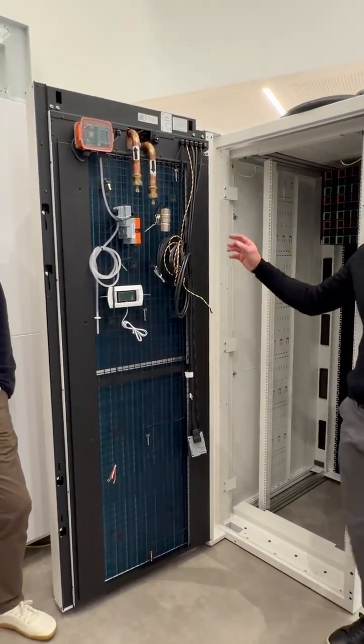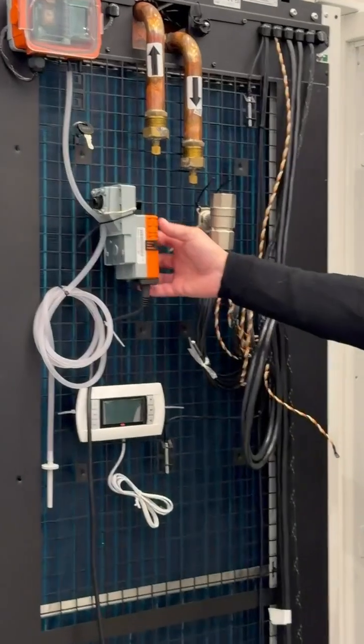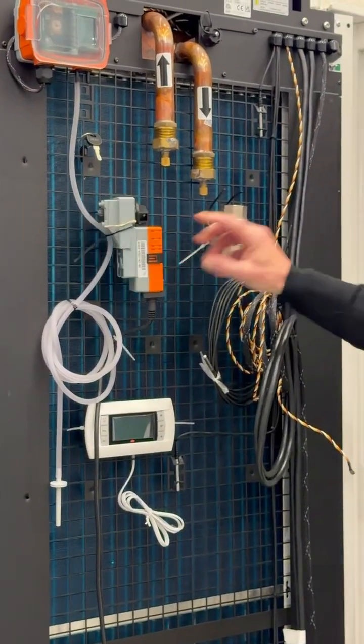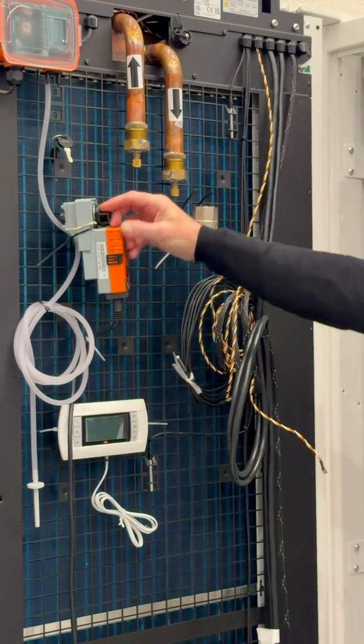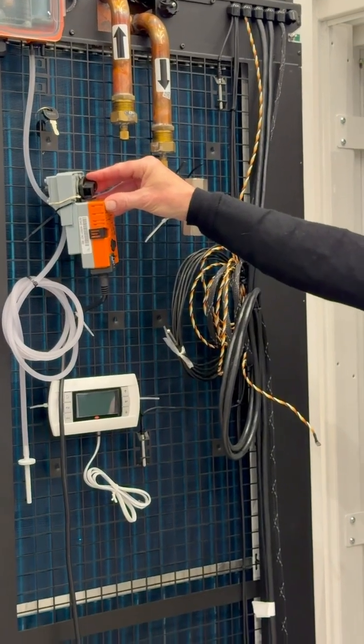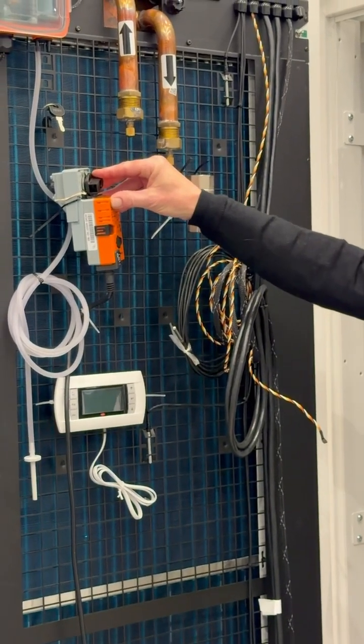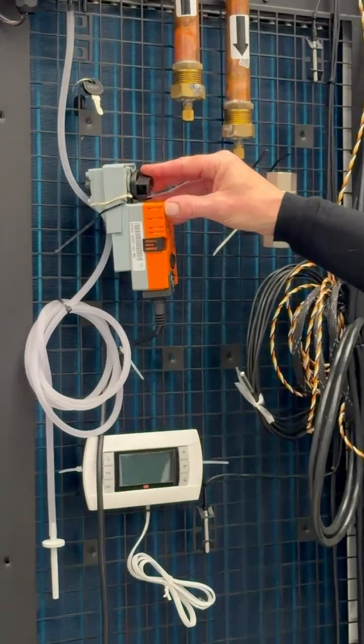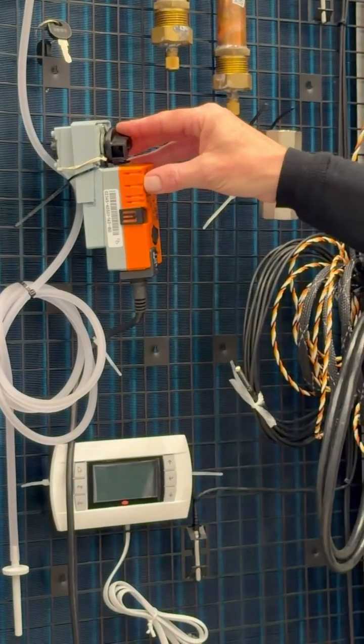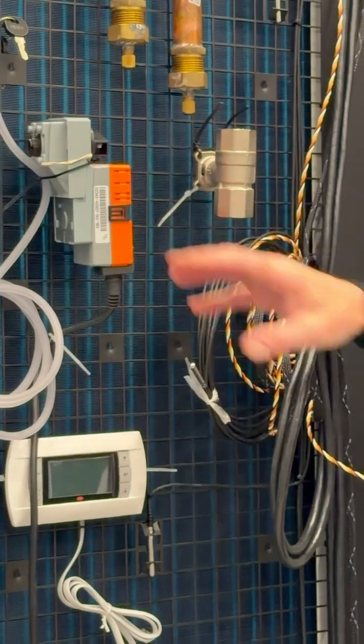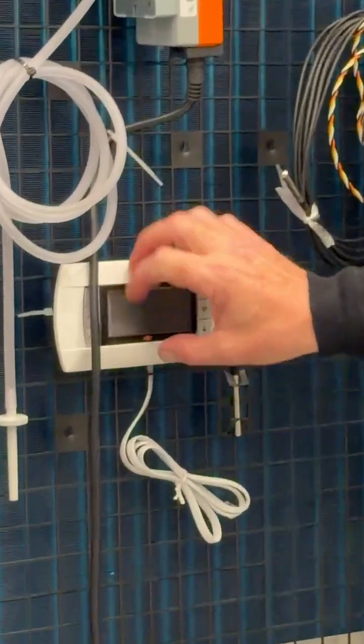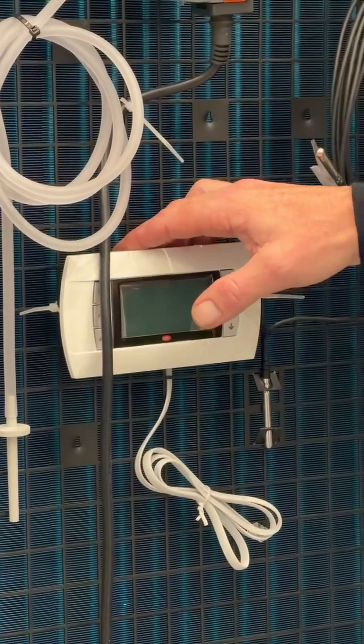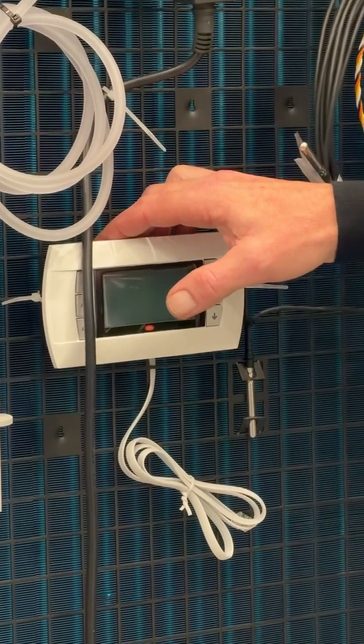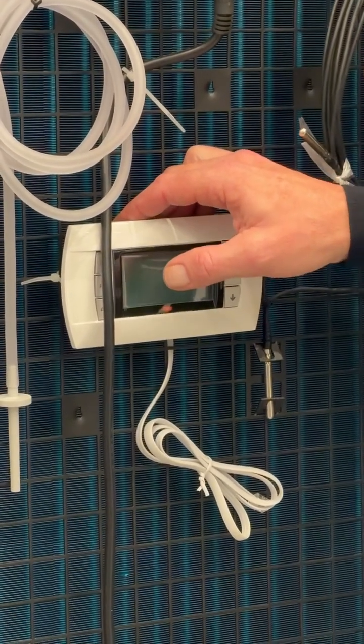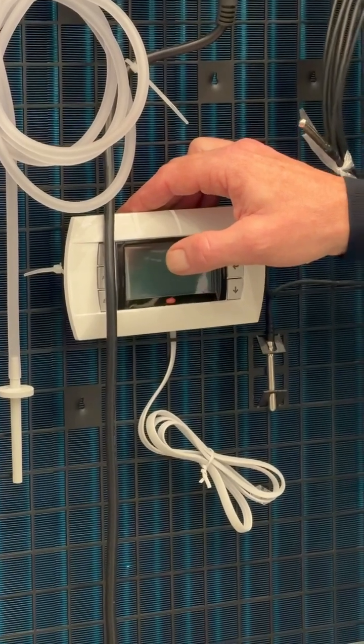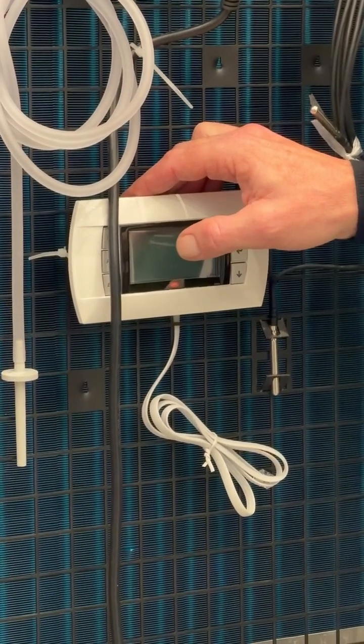We also have a couple of things in there. So you'll see here these valves. So this is called an actuator valve, and a ball valve. So the actuator valve is based on temperature set points. So as different data centers have different flows from 14 degrees in to 32 degrees out, 26 ambient temperature, etc., etc. Part of our role is we commission the door. So whatever the client says, it's not a cookie cut solution. Every data center is different. So we'll go in and we will set the door up to run at the temperature set points that they deem for the facility.